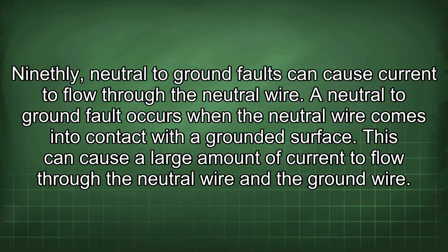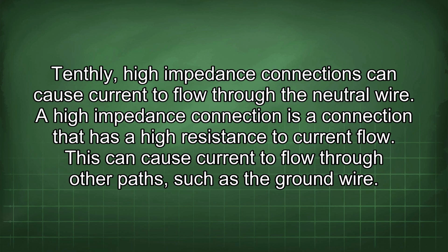Ninthly, neutral to ground faults can cause current to flow through the neutral wire. A neutral to ground fault occurs when the neutral wire comes into contact with a grounded surface. This can cause a large amount of current to flow through the neutral wire and the ground wire. Tenthly, high impedance connections can cause current to flow through the neutral wire. A high impedance connection is a connection that has a high resistance to current flow. This can cause current to flow through other paths, such as the ground wire.